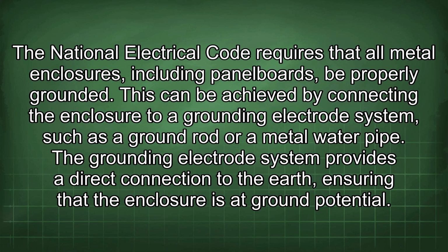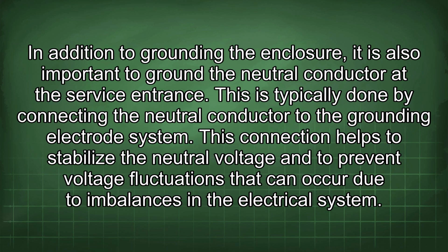This can be achieved by connecting the enclosure to a grounding electrode system, such as a ground rod or a metal water pipe. The grounding electrode system provides a direct connection to the earth, ensuring that the enclosure is at ground potential. In addition to grounding the enclosure, it is also important to ground the neutral conductor at the service entrance. This is typically done by connecting the neutral conductor to the grounding electrode system.